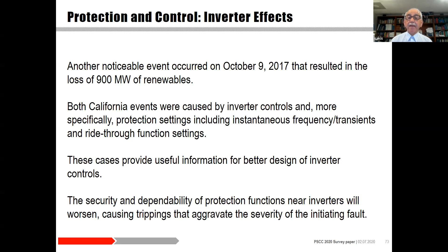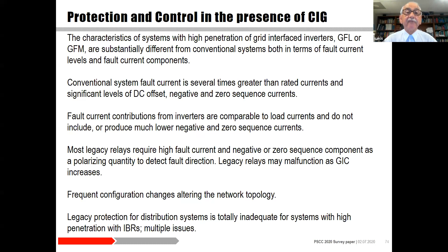Now, to summarize, the penetration of converter interface generation in the power system generates a lot of new problems for protection. I have listed here a number of issues that we have, and as I said, we've seen protection misoperations because of these characteristics of the inverters. So one thing I would like to show you here is that on the top slide, you see a conventional fault in a system with synchronous generators, and you see that the pre-fault current is relatively very small, and during the fault we have a high fault current, we have a DC offset, and, not shown in the slide, we have zero and negative sequence components.